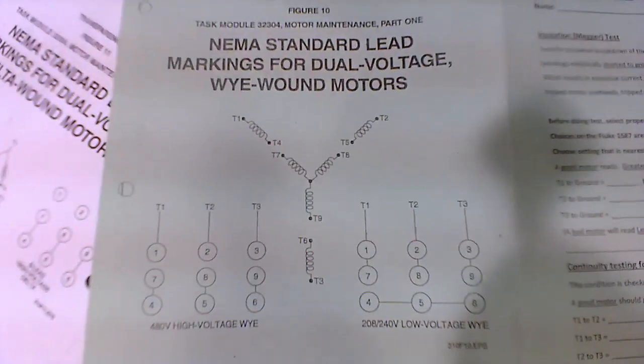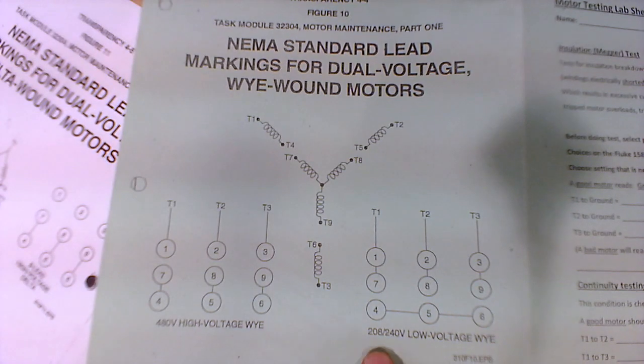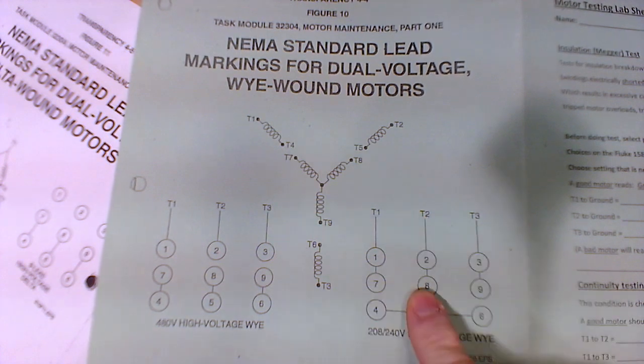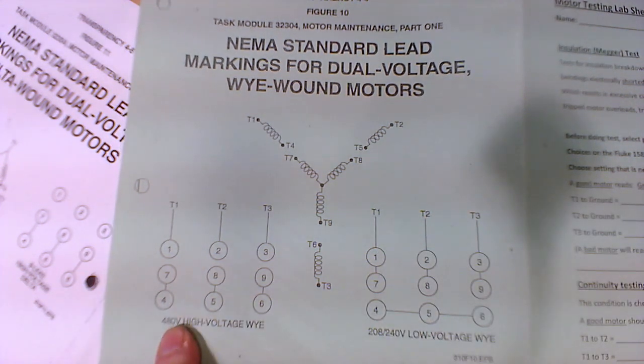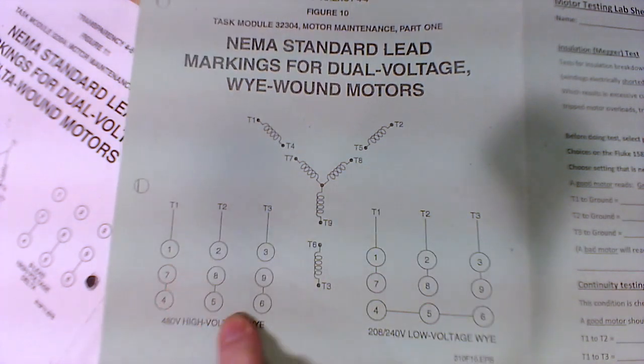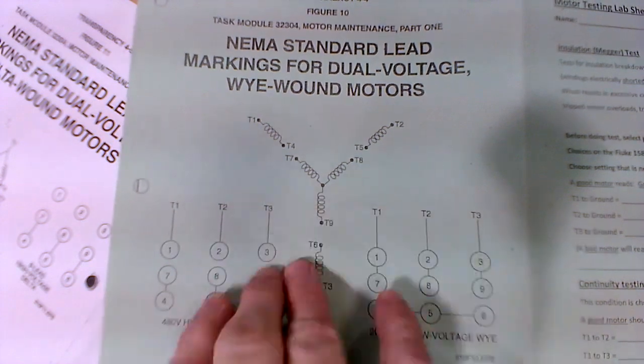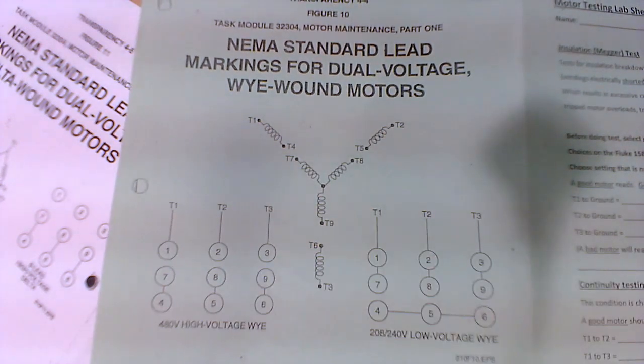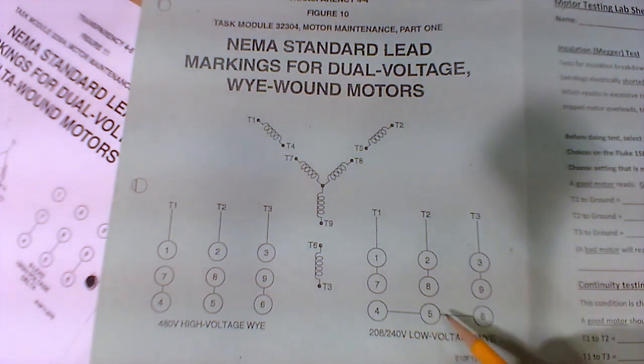with them. That's going to be based on, are you wiring that motor for low voltage, which will be in the range of 208 to 240. If you're going to go low voltage, you do this configuration with your wire nuts. If you're going to go high voltage, 480, or maybe as low as from 460 to 480, you would do this connection with the wire nuts, and that same motor would run on low voltage or high, and it would run the same horsepower. No difference in horsepower. And so let's talk about how you do it if this motor is going to run on, say, 240 volt three-phase.